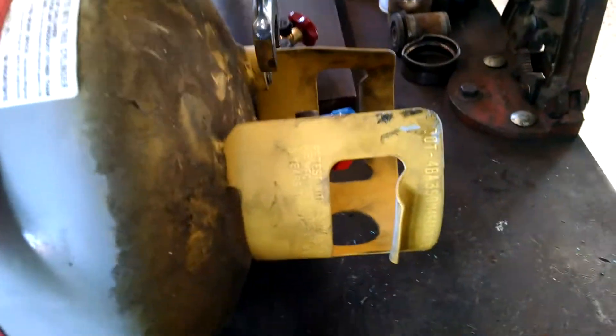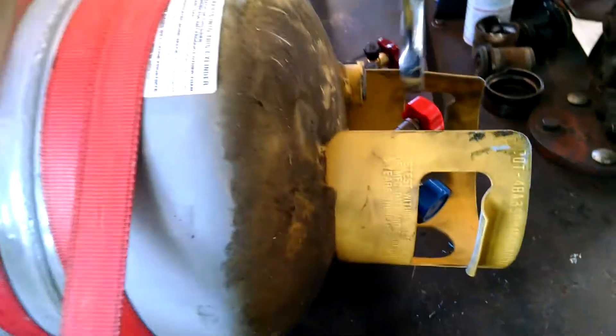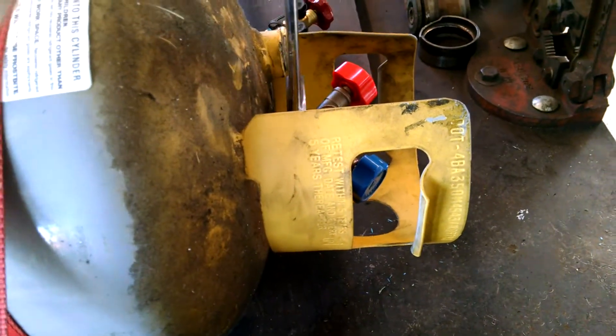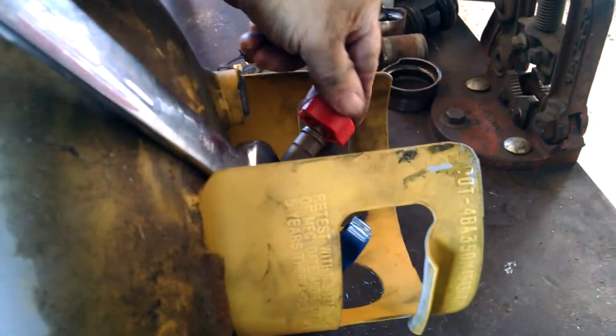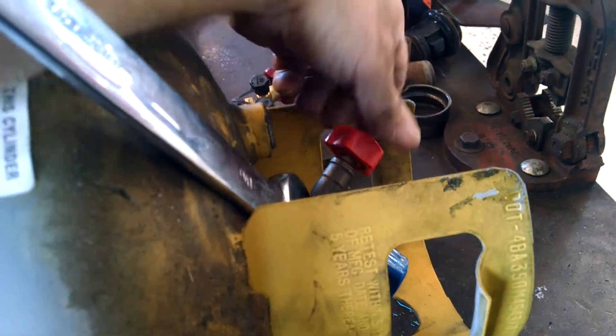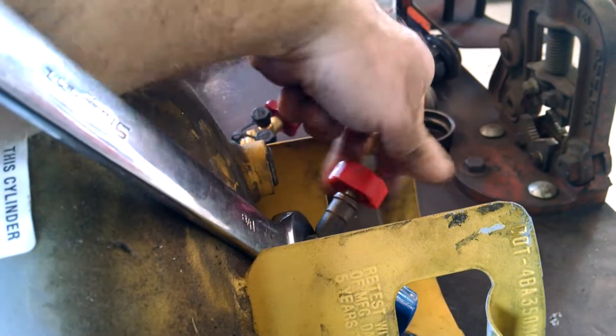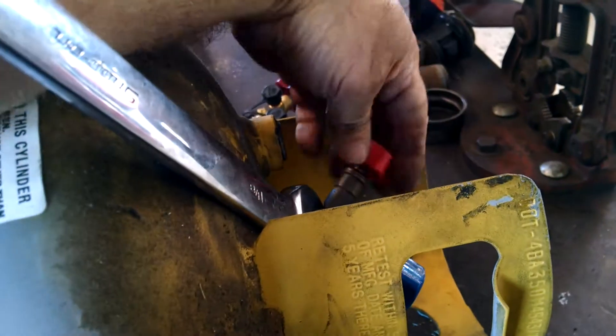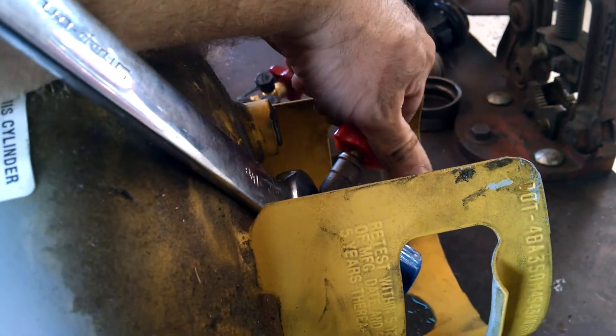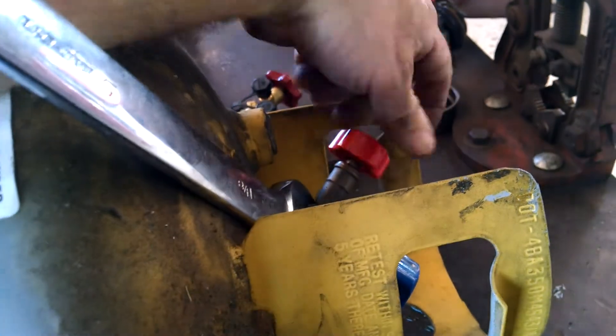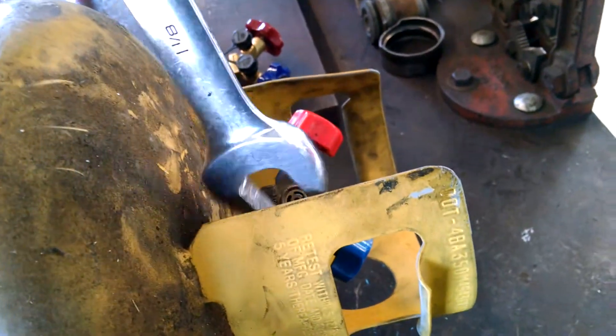I should probably have somebody holding the camera. I want to get a better picture of it there. See, the valve internally is turning. It just doesn't ever tighten up. So we'll risk losing all of our Freon in the atmosphere if there's a leak, and that's not good for the environment. So that's the reason why we're going to change this valve.